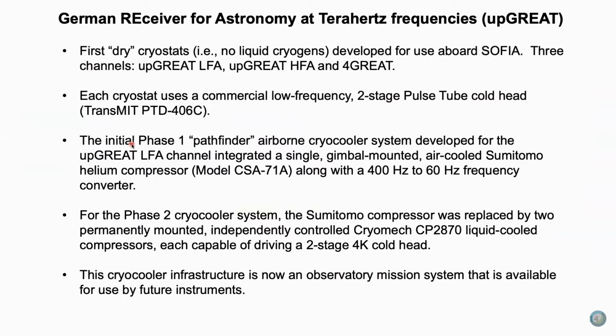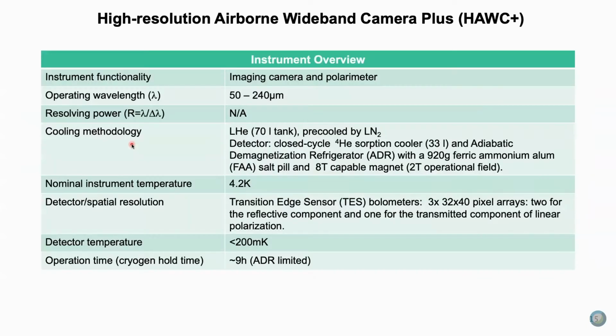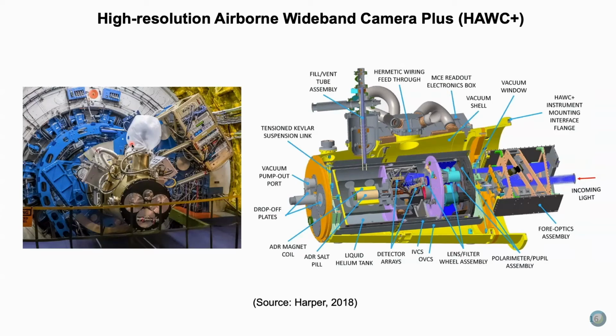So, like I said, this is the first dry cryostat. Each cryostat uses a commercial low frequency, few hertz, 2-stage pulse tube cold head. Initially, a Sumitomo helium compressor was installed especially for this. Later on, SOFIA made the decision to install permanently 2 compressors, which could be used by future instrument developers. So the cryocooler infrastructure is now an observatory mission system that is available for use by anybody.